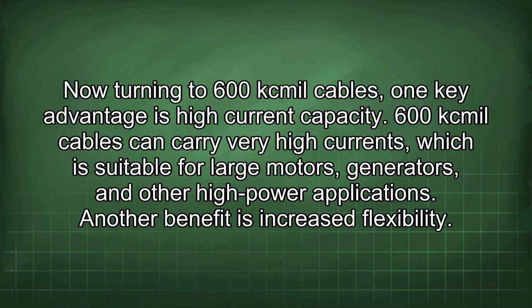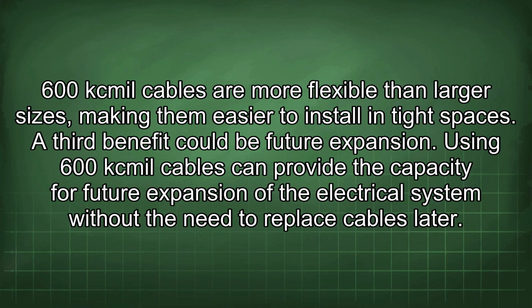600kcmil cables can carry very high currents, which is suitable for large motors, generators, and other high-power applications. Another benefit is increased flexibility. 600kcmil cables are more flexible than larger sizes, making them easier to install in tight spaces. A third benefit could be future expansion. Using 600kcmil cables can provide the capacity for future expansion of the electrical system without the need to replace cables later.